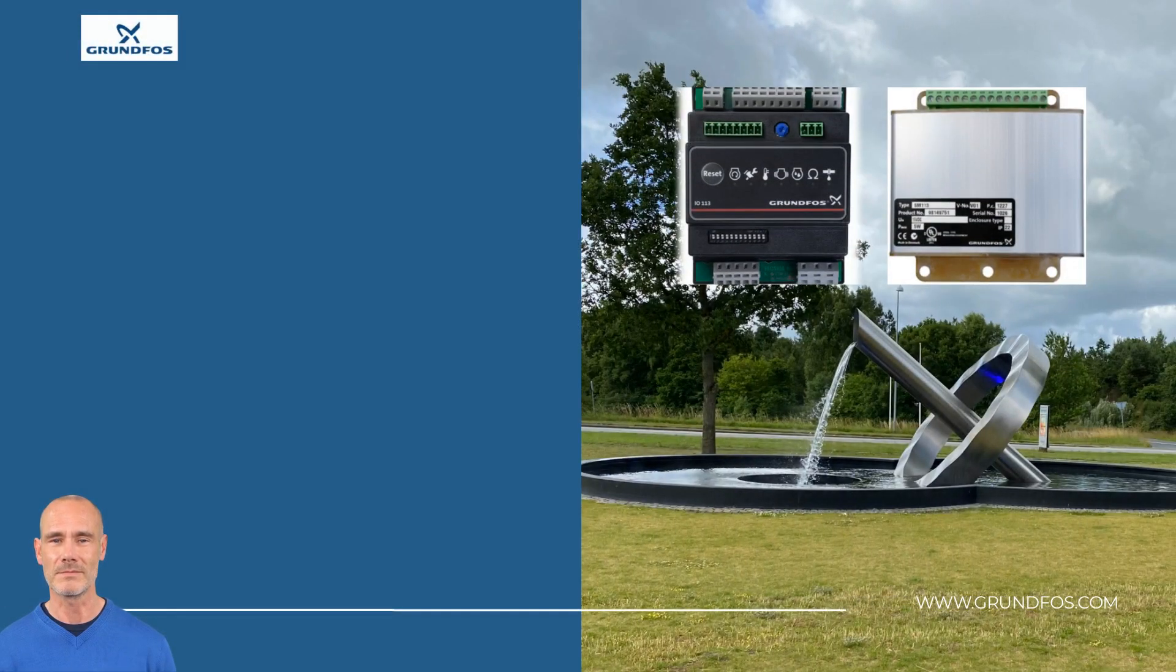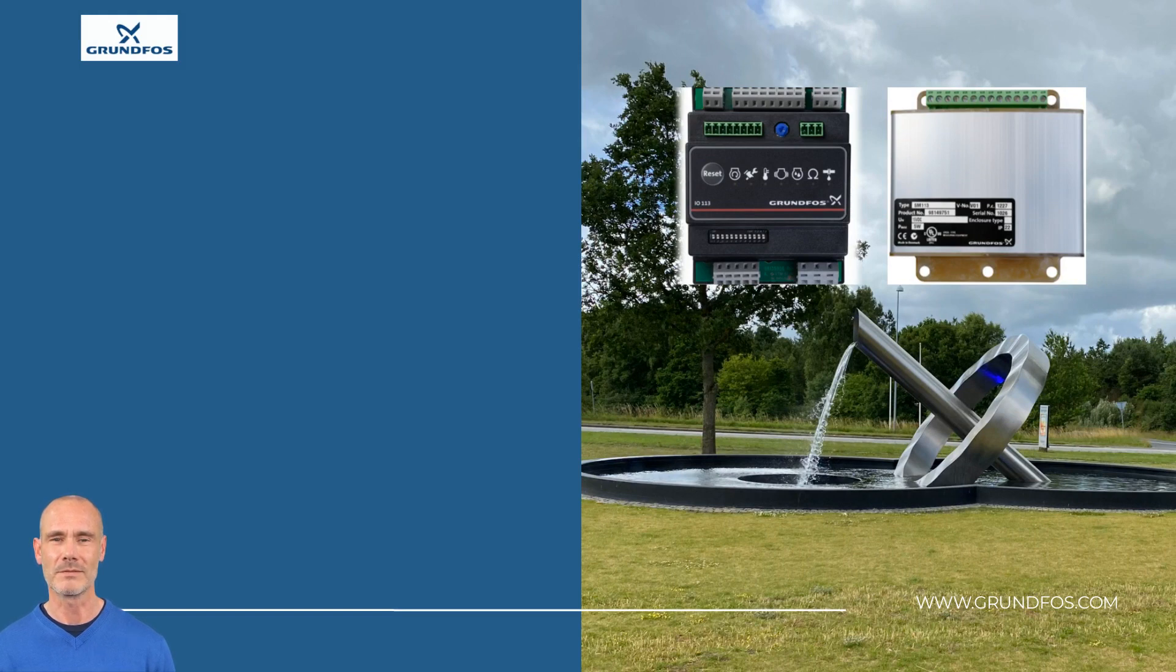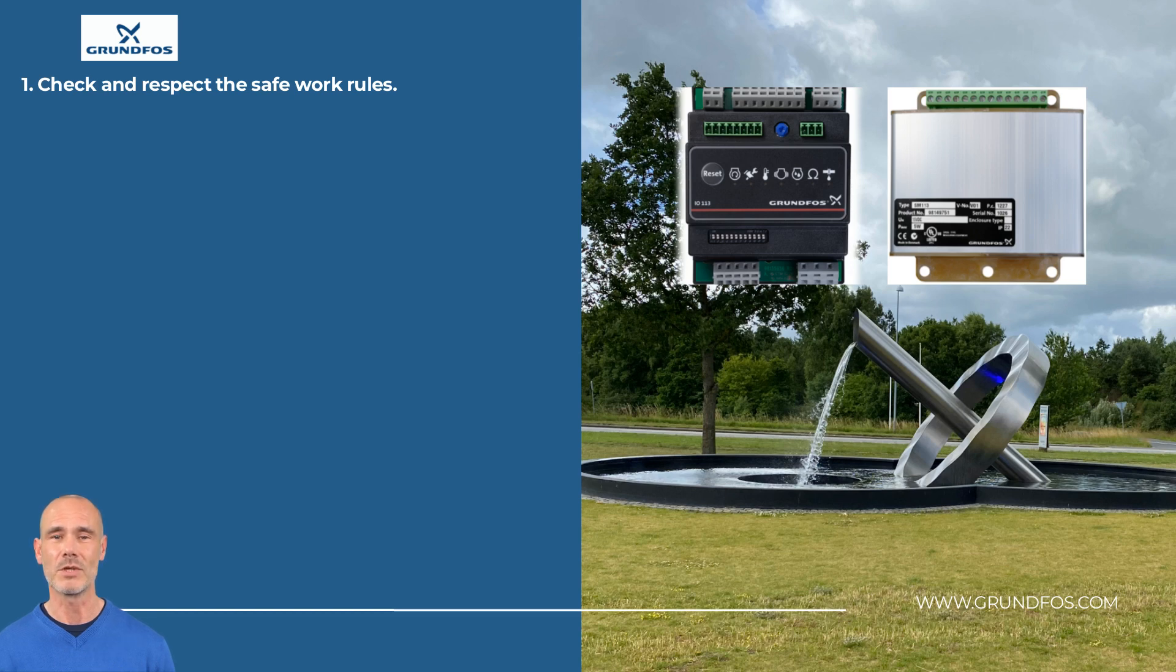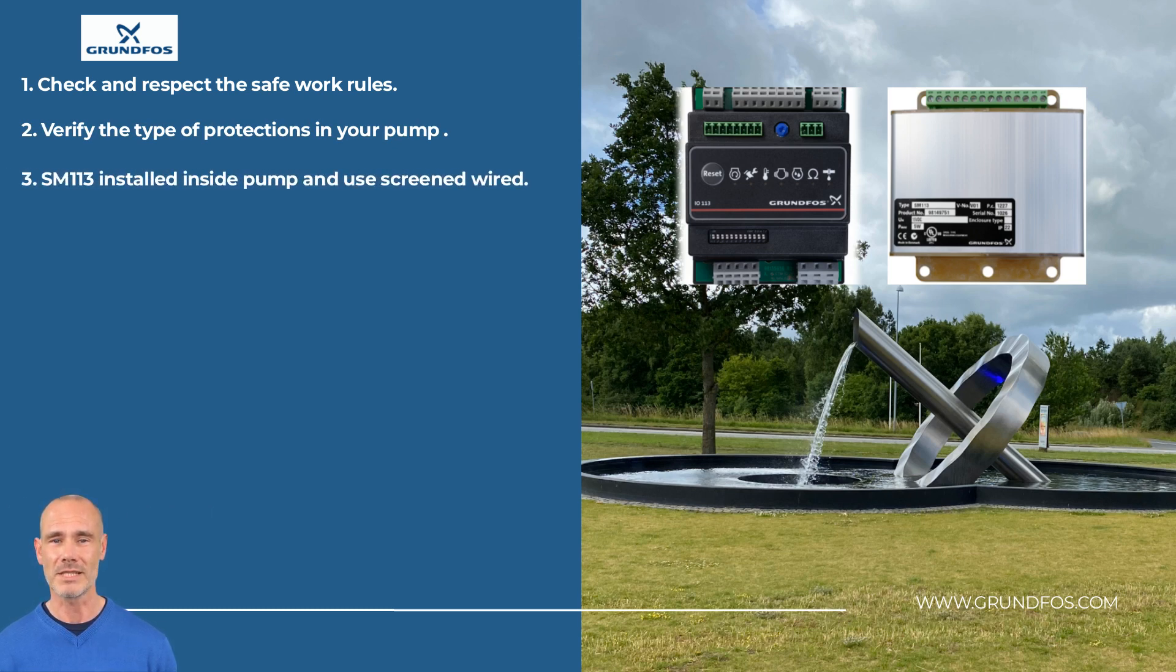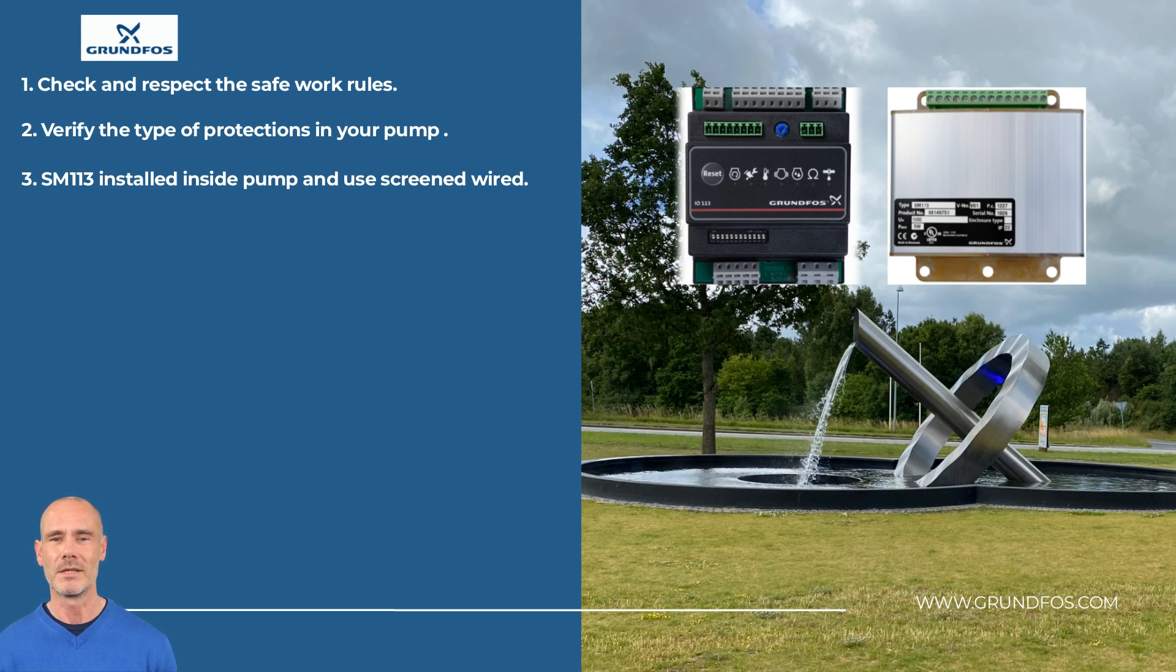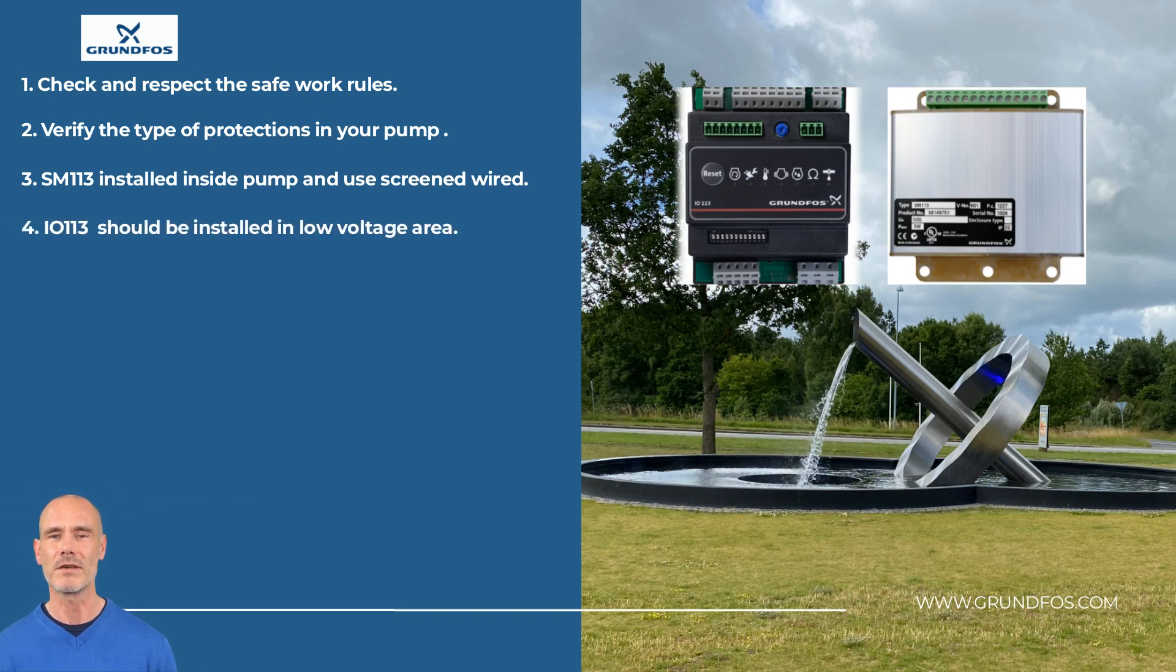We have arrived at the end of this video. Please remember: take all preventive measures to avoid accidents during the work. Previous to the DIP switches configuration and wirings, check the type of protection and the sensors in your pump. The SM-113 installation should be inside the pump. Use screened cable to reduce the noise from other electronic devices. IO-113 should be installed in a low voltage area.